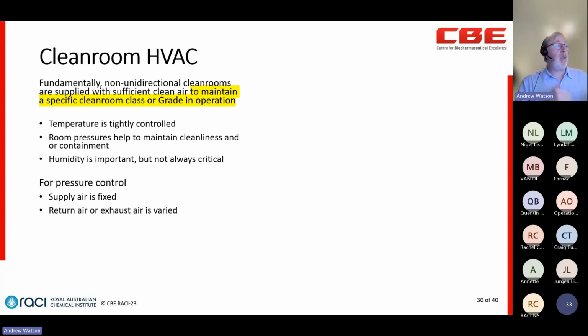For pressure control, you fix the supply air and vary your return and exhaust air. If you want a positive pressure, you put a little more air in than you're taking out. If you want a negative or lower pressure than surrounding areas, you take a little more out than you're putting in.